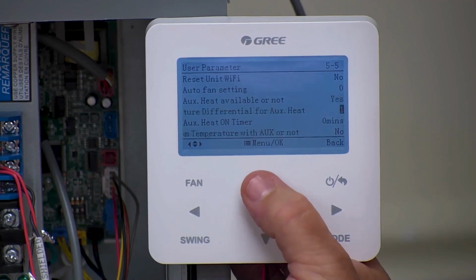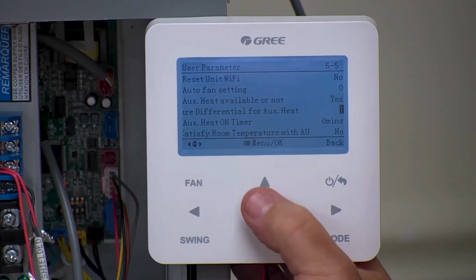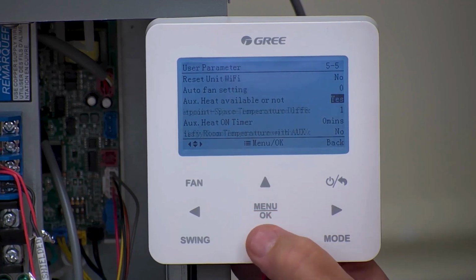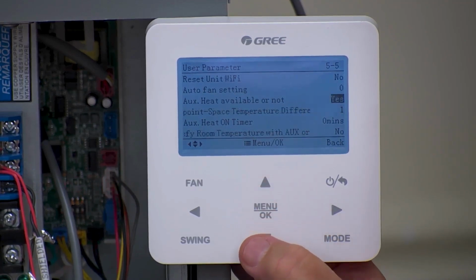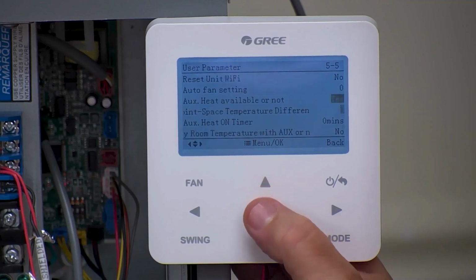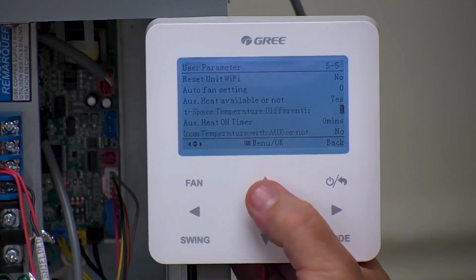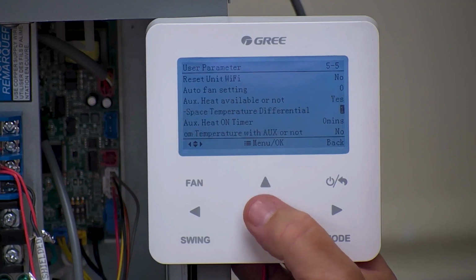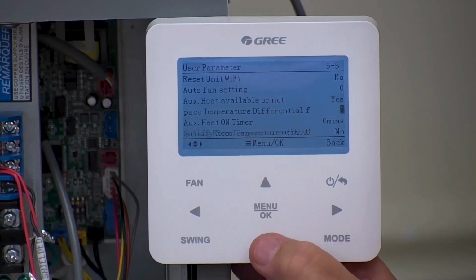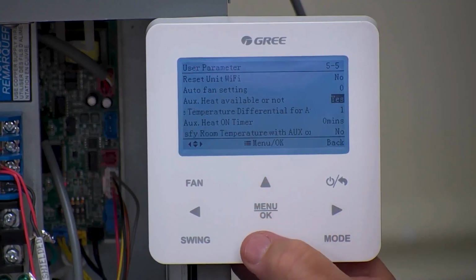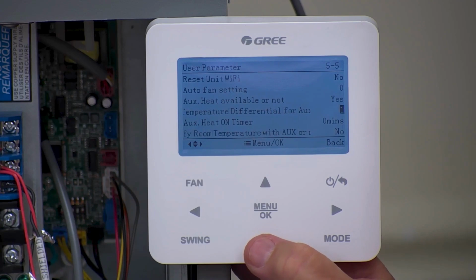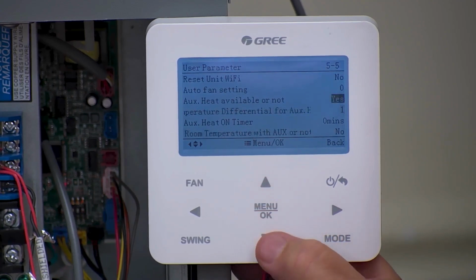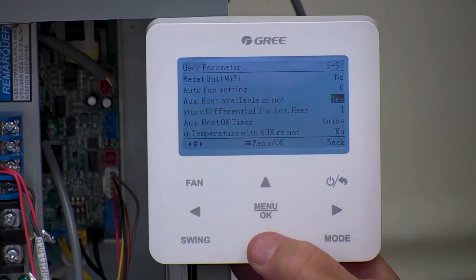So if you don't want to lose your page and you're trying to focus on something, just keep hitting up and down or left and right and it'll keep you there until you're ready to move on. So anyway, what that differential is, that's basically your differential between your first and second stage. So right now I've got it set to 1, and you can go between 1 and 10. So basically you can have this set up to where you've got a 1 degree differential between the heat pump running. If we slip another degree, then it's going to bring on the electric heat. If it doesn't slip that degree, it's not going to bring on the auxiliary heat.